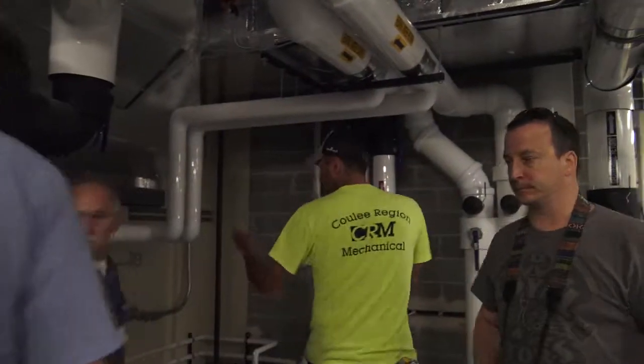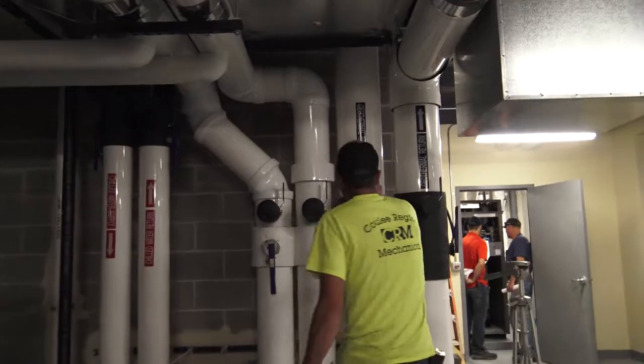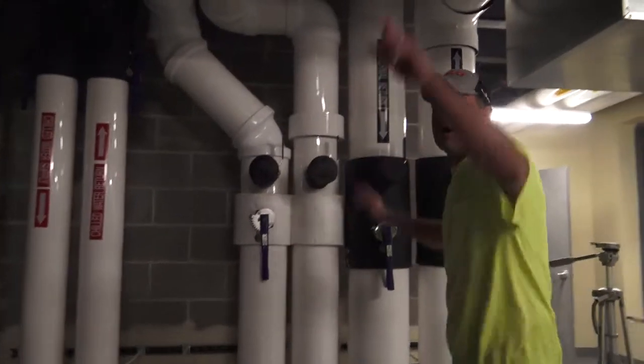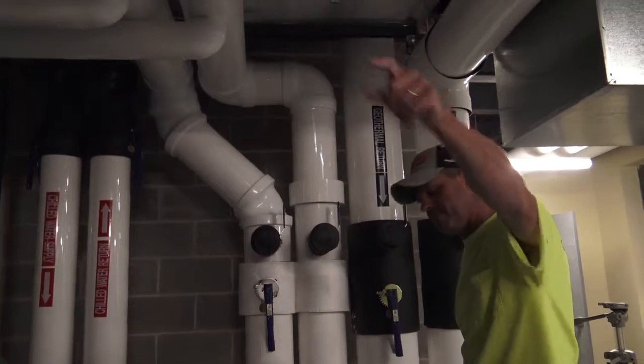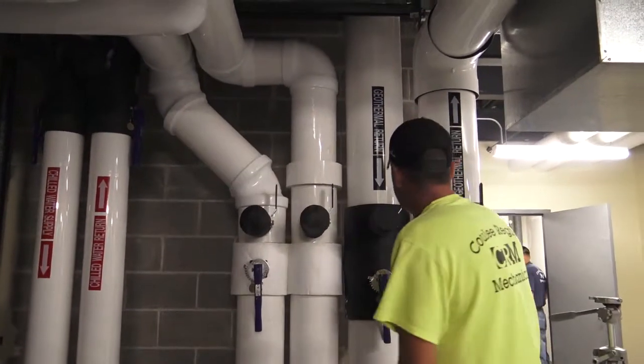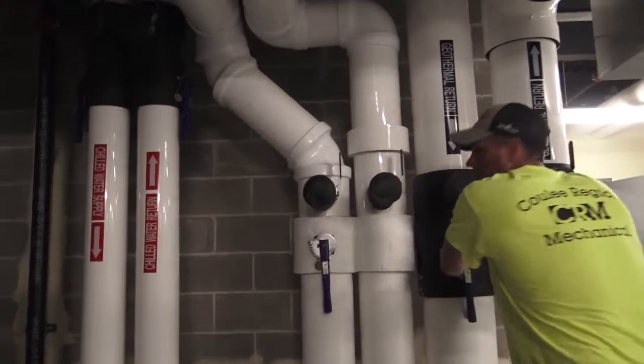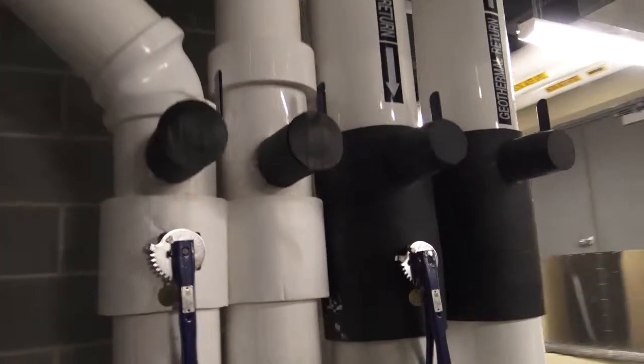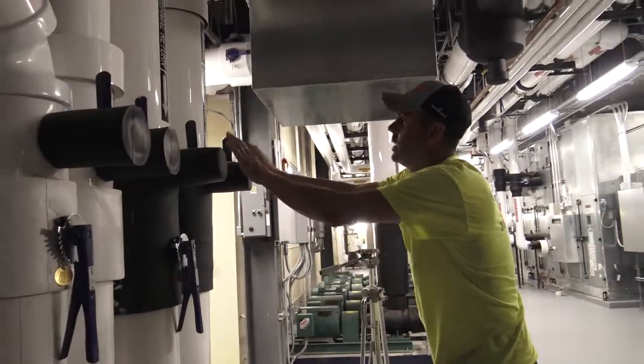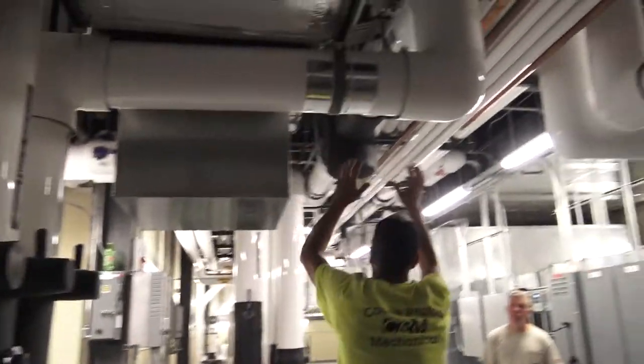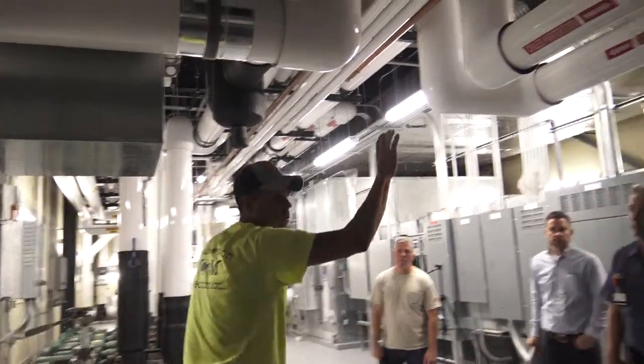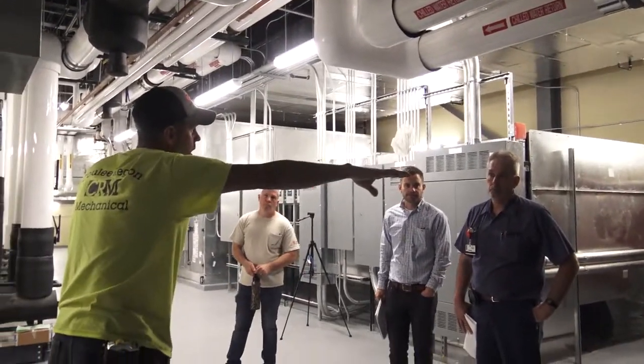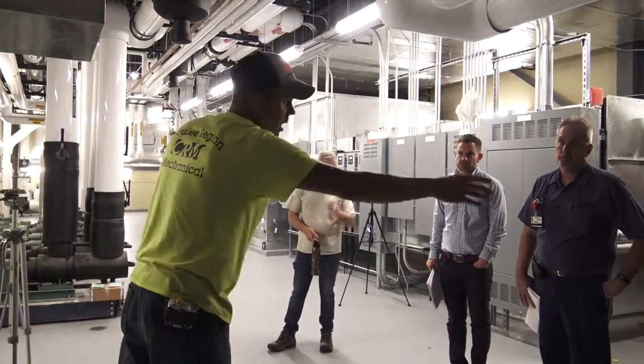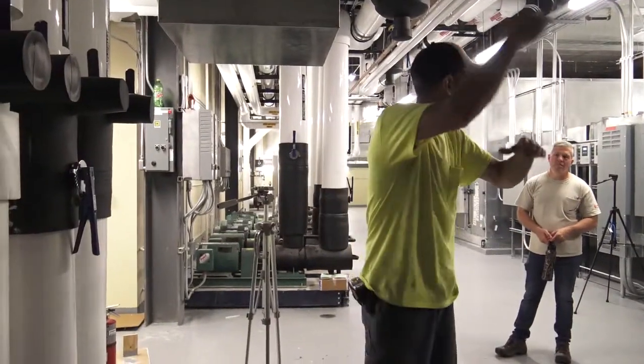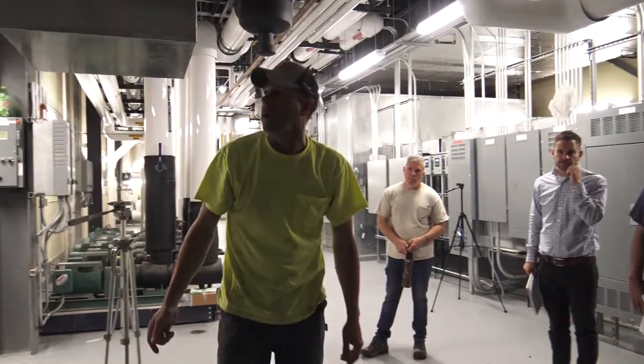And these over here are your valves for heating the homes or whatever. This right here is your geo, that's coming down out in that corner where the break room is. So if you shut these off, make sure the pumps are down, make sure if you've got problems up here, these two right here only take care of what's ever here. You've got valves where that comes up through the ground, I'll show you later, that'll take care of from the ground up to here. If you ever have problems on the first or second floor, then we'll take care of that.